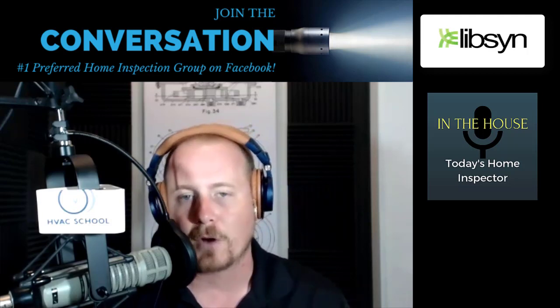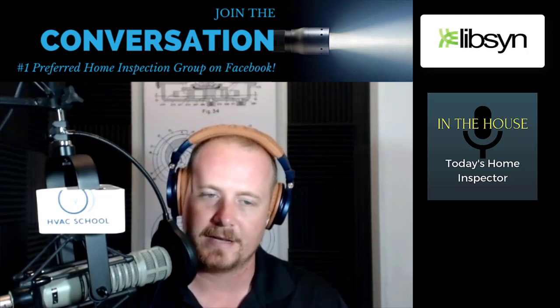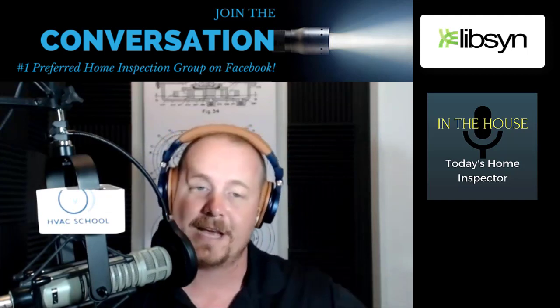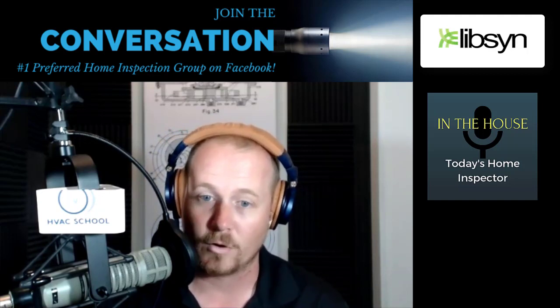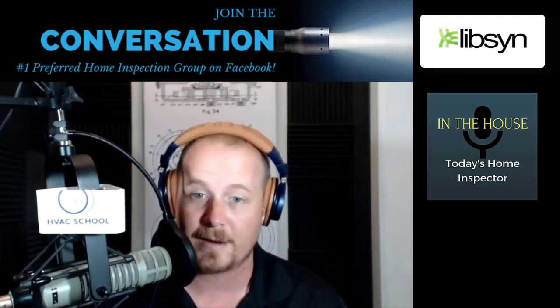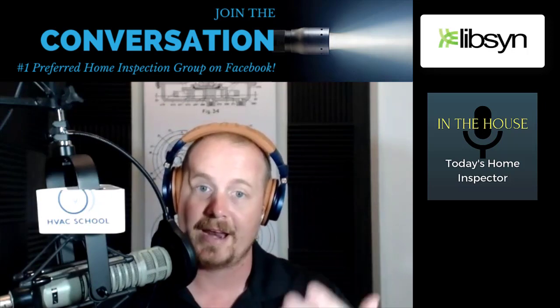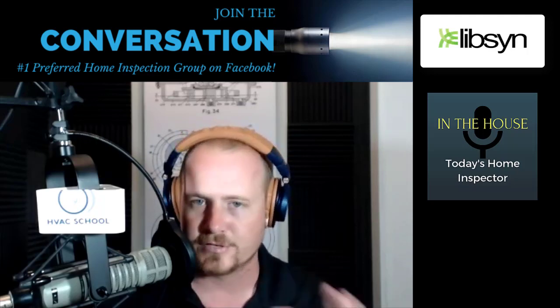And so the problem isn't so much that measurement means nothing. It's that it gives a false positive. It gives the impression that there's something wrong when there isn't. And on the other end, taking vent temperatures can also give you the sense that there's nothing wrong, and you could very well have a frozen evaporator coil. You could very well have very cold vent temperatures and actually have a system that has significant problems with it. And so there's all of these challenges.